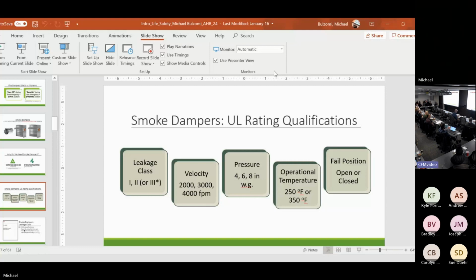Fail position. Are we designing smoke control systems in here? Okay, this is where it's very important. If you have the need for a damper to fail open so that ductwork can continue to be used for smoke control in the event of a loss of power, you've got to put that note on the drawing somewhere or in the spec. If I ship a damper that's rated for fail closed, all the stars have to line up perfectly for me to be able to send a letter to somebody to say, you can flip the actuator over and use this for fail open.